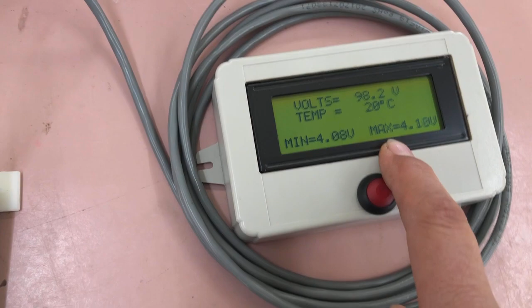At the moment, because the outputs are on, everything's okay - every cell is above the low voltage threshold and below the high voltage threshold. All these can be set up in the configurator here. BV means the balancing voltage has been reached by at least one cell, which is true since it's past 4 volts, our current balancing voltage. Temperature is okay, and the overall BMS is okay.